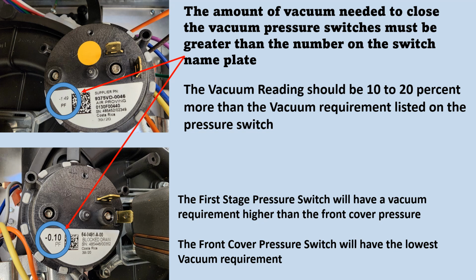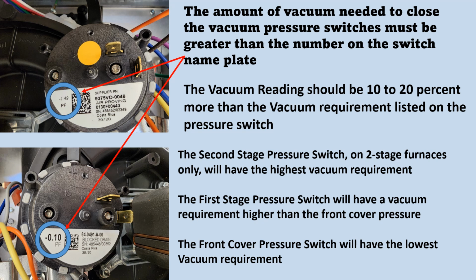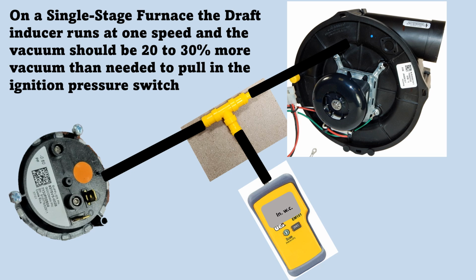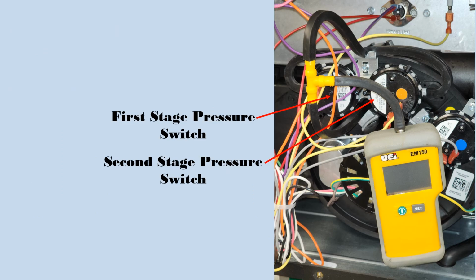The first stage pressure switch will have a vacuum requirement higher than the front cover pressure switch. The second stage pressure switch on 2-stage furnaces only will have the highest vacuum requirement. On a single stage furnace, the draft inducer runs at one speed, and the vacuum should be, and I put 20 to 30% here. I forgot to correct it, but it can be 30% more. Just all depends. More vacuum than needed to pull in the ignition pressure switch. First stage pressure switch and the second stage pressure switch are marked there.